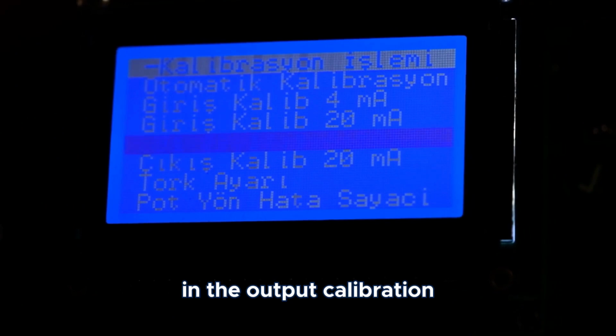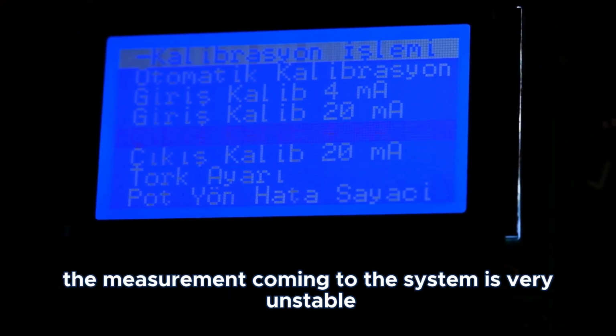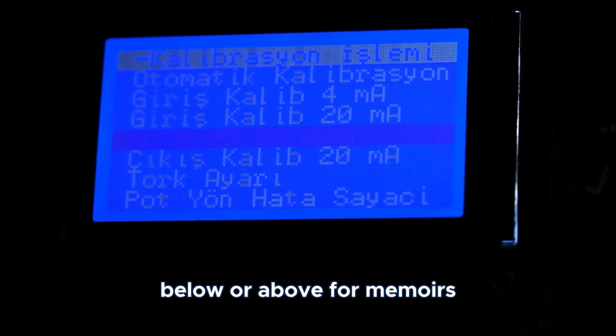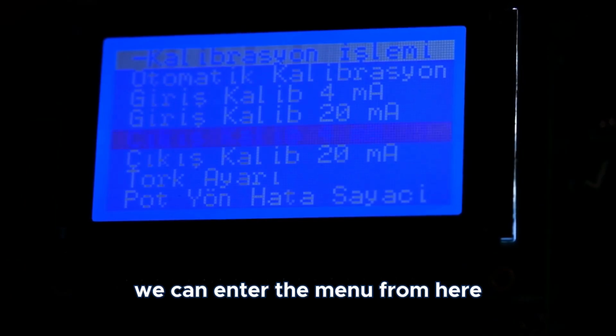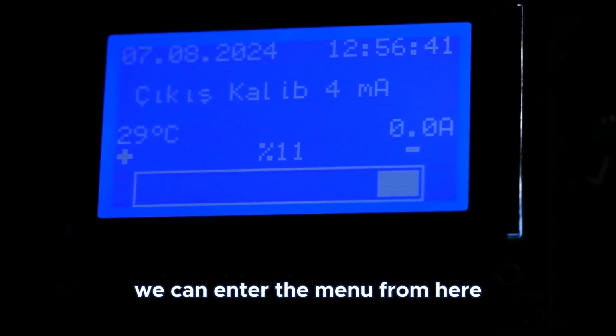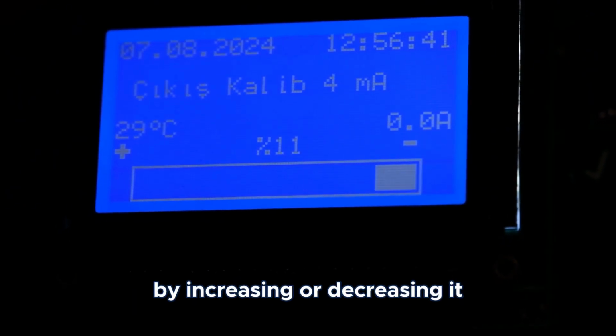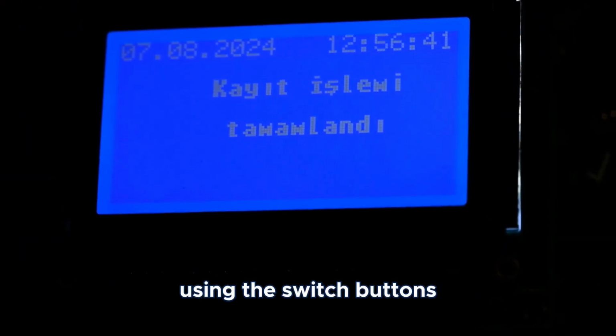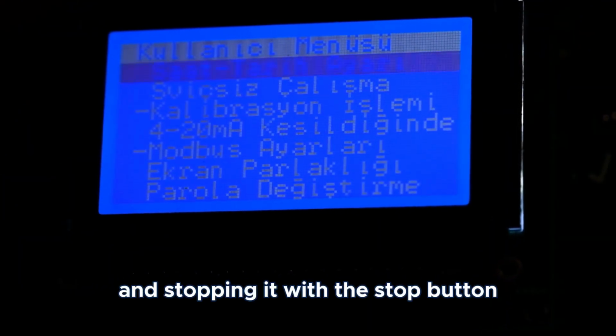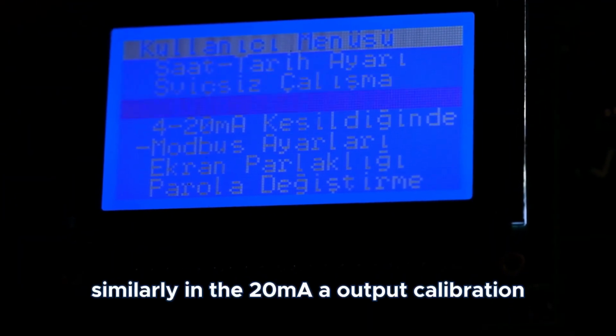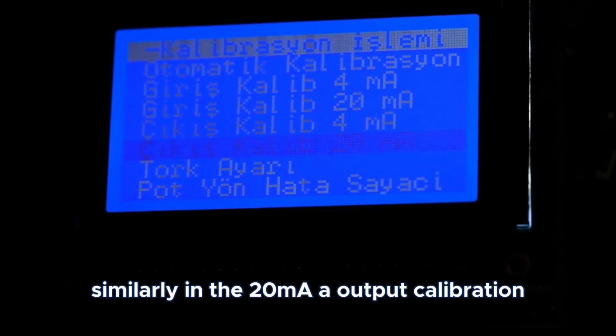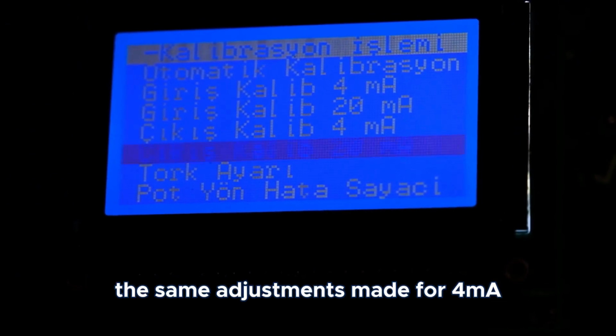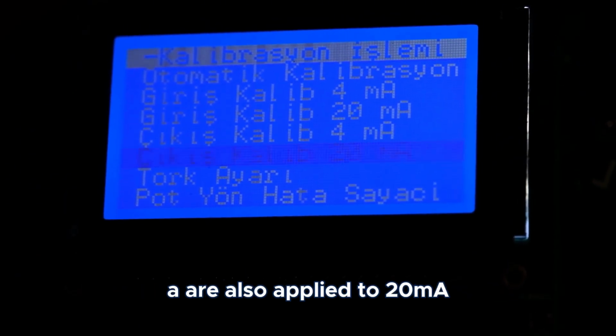In the output calibration, if the measurement coming to the system is very unstable below or above 4 mA, we can enter the menu from here and complete the process by increasing or decreasing it using the switch buttons and stopping it with the stop button. Similarly, in the 20 mA output calibration, the same adjustments made for 4 mA are also applied to 20 mA.